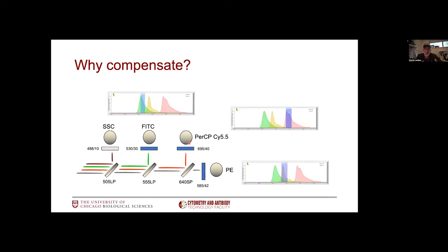What we also said is that the system is somewhat imperfect because of the wide emission range of each of these fluorophores. It's quite possible that the light coming from one fluorophore will bypass the dichroic mirror and end up in the wrong channel generating false positives. That's what we're going to call spillover or bleeding.